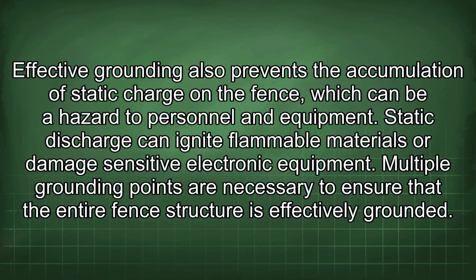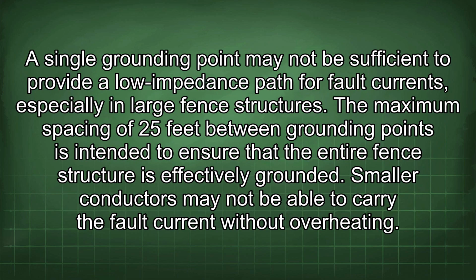Multiple grounding points are necessary to ensure that the entire fence structure is effectively grounded. A single grounding point may not be sufficient to provide a low impedance path for fault currents, especially in large fence structures. The maximum spacing of 25 feet between grounding points is intended to ensure that the entire fence structure is effectively grounded. Smaller conductors may not be able to carry the fault current without overheating.